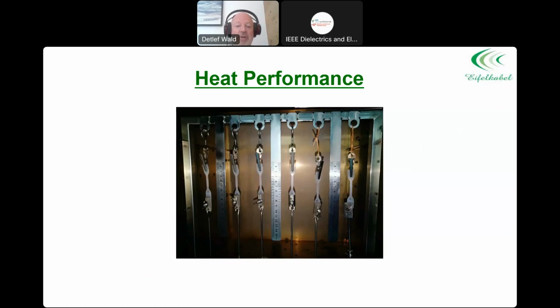What we also did, and now you might be surprised, this looks like a hot set test. This is a test that we have done and presented some years ago at Jicable in a session in Paris. That was before Corona, so that's the new time counting. We compared polypropylene with XLPE. We didn't go at the normal test. Heat elongation is done at 200 degrees, 15 minutes. So we did it at 135 degrees and a longer time, and that has been done for 42 days.